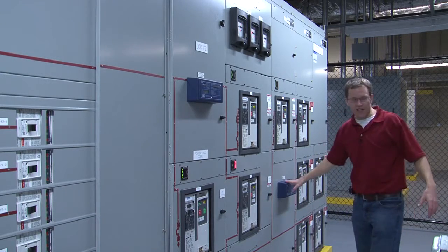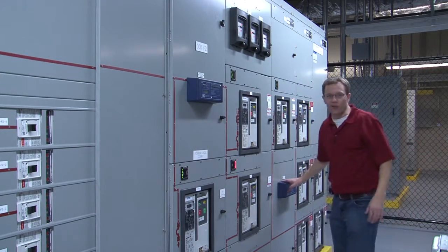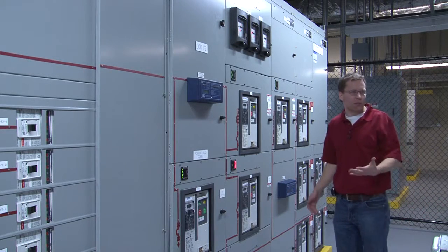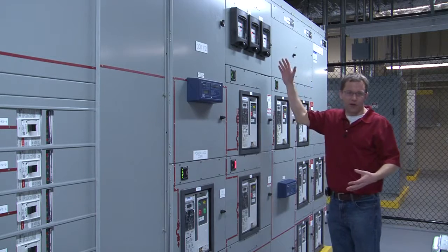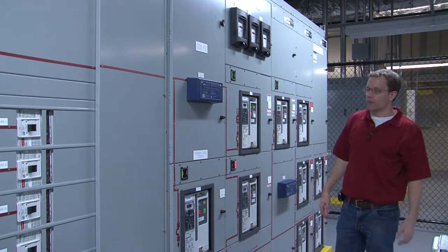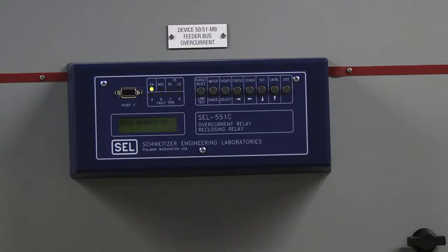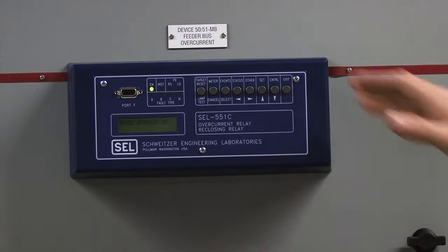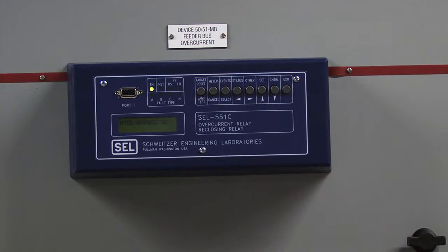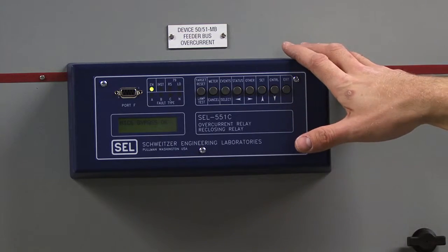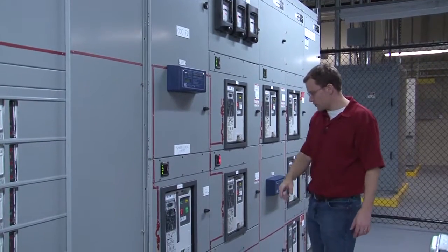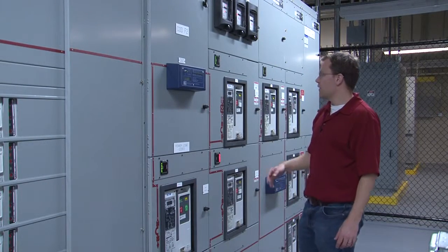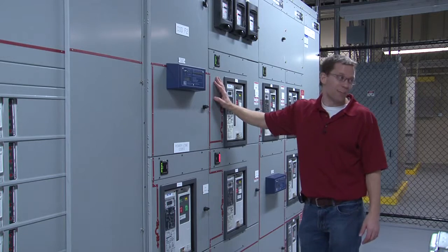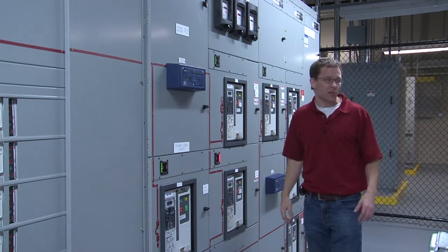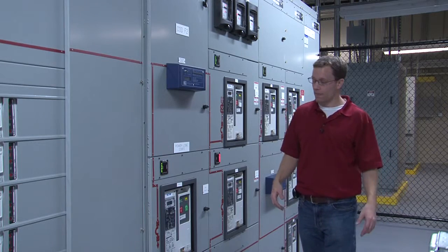All right, now in this case there are two separate SEL relays. I don't really know why they chose to use this model relay here and a different model over there, but they did. The real difference between these two and that one is that one has essentially two relays embedded into one box. Here they use two separate relays. So one relay handles an overcurrent on the main bus coming from the UPS modules, and the other one handles an overcurrent on the maintenance bypass source bus duct. So it'll send something to Square D to the effect of don't transfer, we have some sort of an overload.